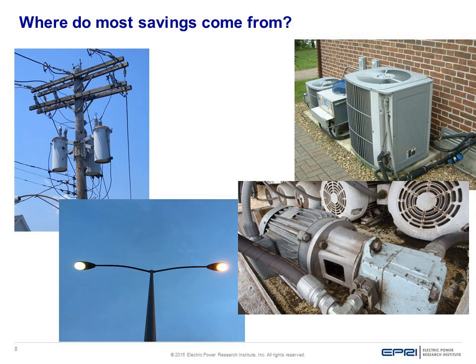Some other equipment, like the transformers in the upper left, or the motors in the bottom right of the screen - when you lower voltage to a motor, most of the time you're actually making it run more efficiently. It's running cooler, so you're getting the same output for less input. In the case of motors, you're not reducing output, you're just getting an efficiency gain, particularly with lightly loaded motors that have less mechanical loading on them. When a motor is running really hot with a heavy mechanical load, there can be a sweet spot where lowering voltage gives some benefit, but lower it a bit more and it starts to get worse.